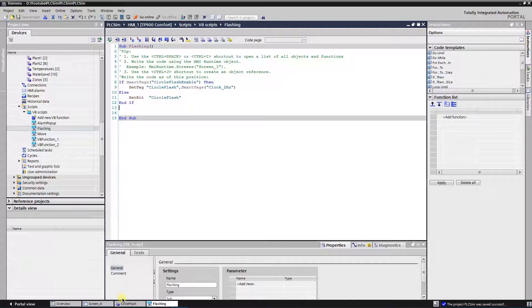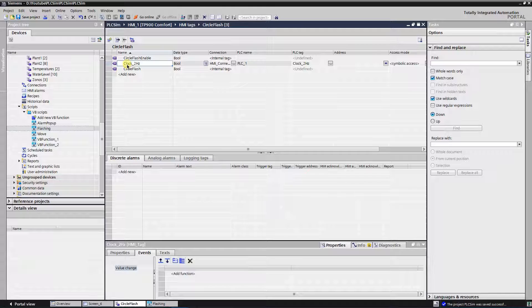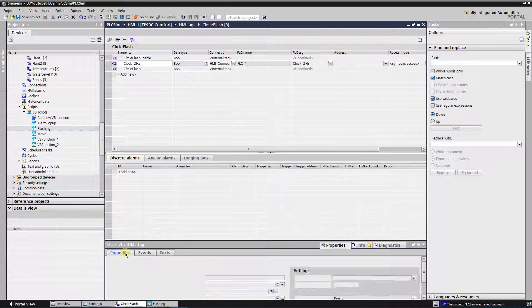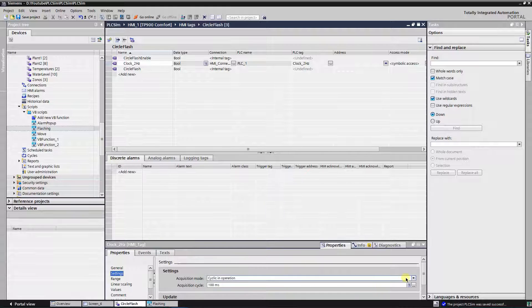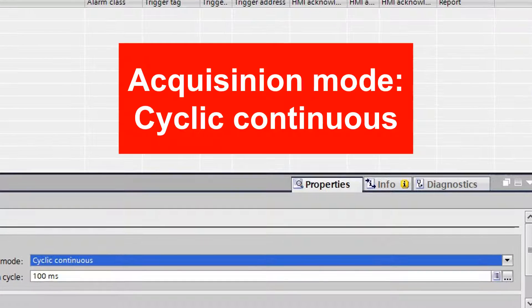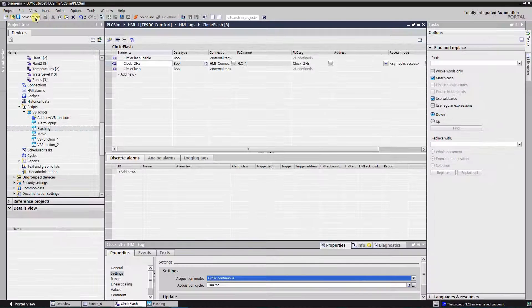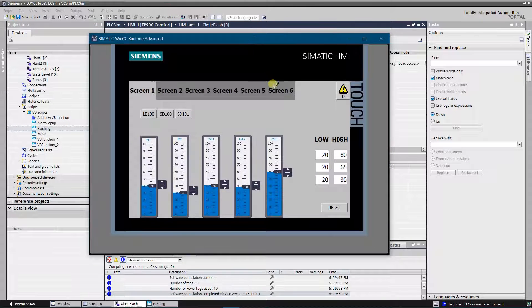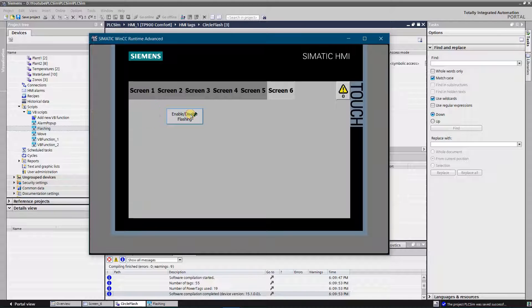Scripting is done. Now we need to fire our script on a tag value change event. Open the tag table and select the 2Hz cycle tag. Switch to the events tab, and on the value change event select the newly created VB script. There is one more important step needed — otherwise your application will not work. Switch to the properties tab of the tag, select settings, and change the acquisition mode to cyclic continuous. All is done, let's test it. The circle is visible all the time unless flashing is enabled.